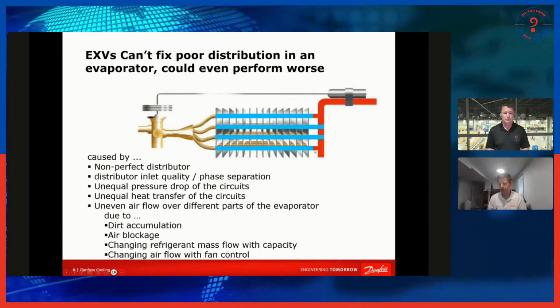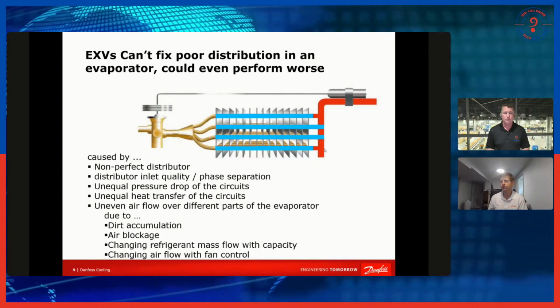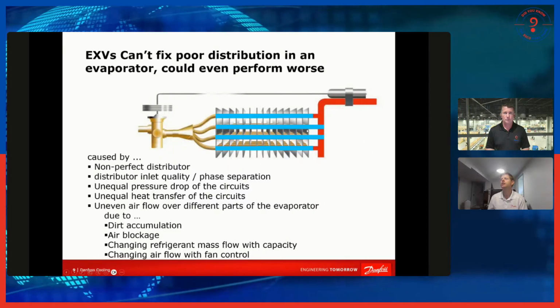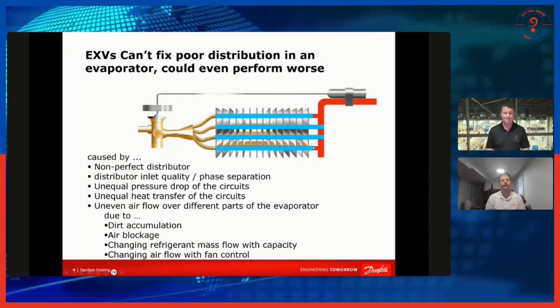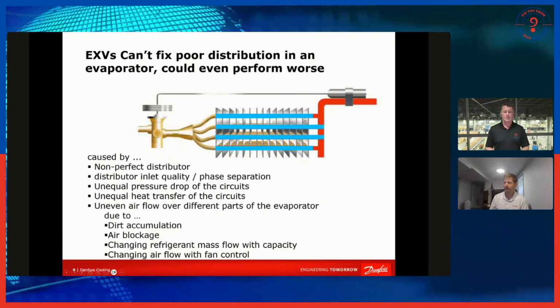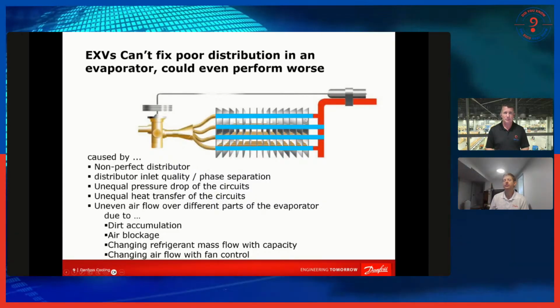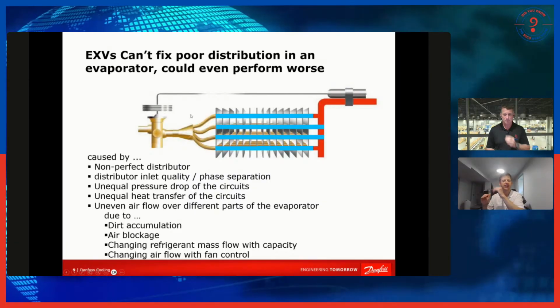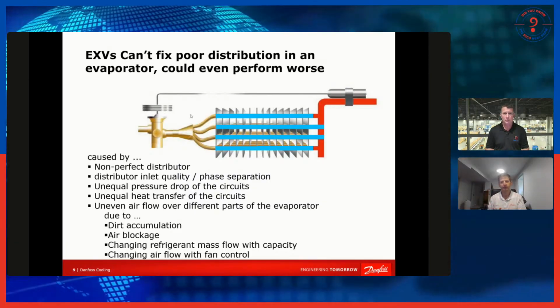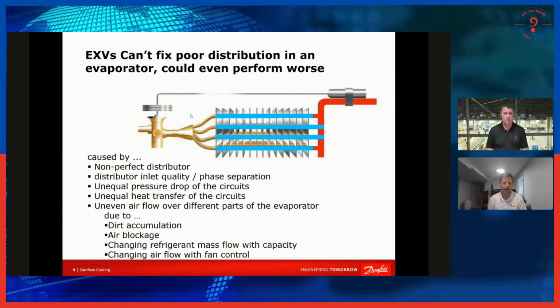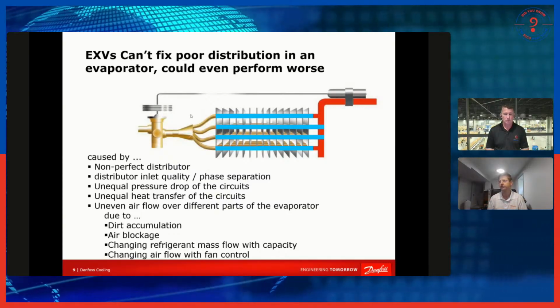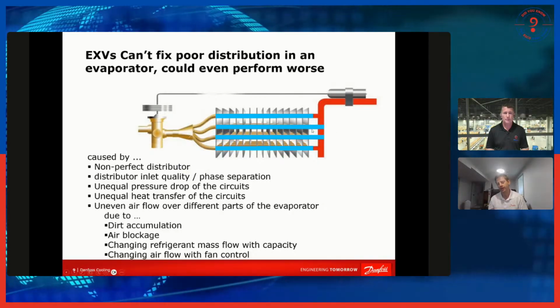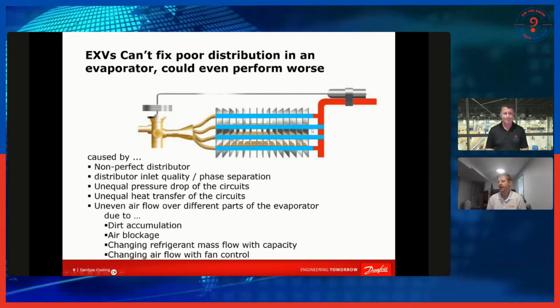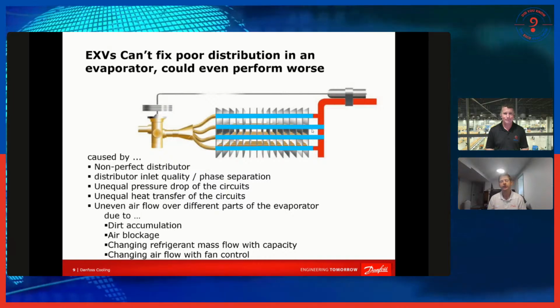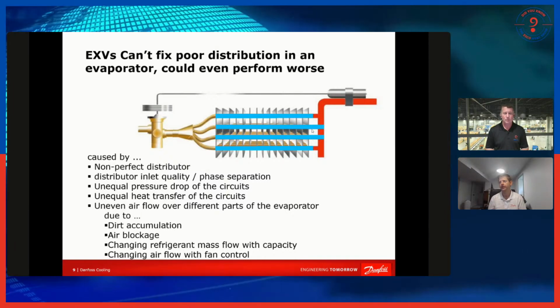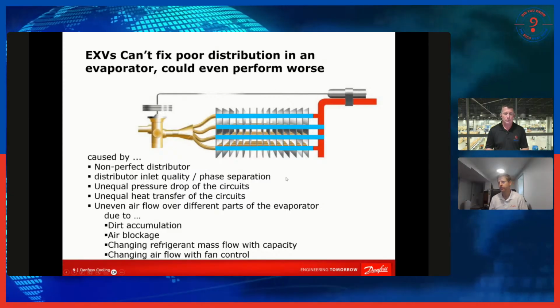And then when you're setting the superheat, whether it's with a TXV or an EXV, you set it so that you get it as low as you can, but have none of those circuits flooding back. So if you were to measure superheat in each one of these circuits, you might see some of them are at 3 degrees and others are at 10, and then it all averages out. And what you need to make sure, and this comes from manufacturers that are testing systems, is that they never get to zero in any of those circuits. That's generally how a TXV or EXV's superheat set point gets determined, to make sure you don't have flood back through any one of these individual circuits.